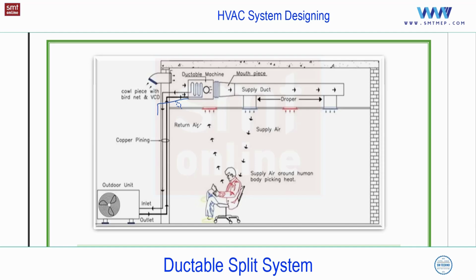So this drain pipe also requires insulation, because in this image here you can see the outside wall, but suppose the room is extended, then the drain pipe will run maybe 10 feet or more than that with the proper slope. So insulation is required for this drain.